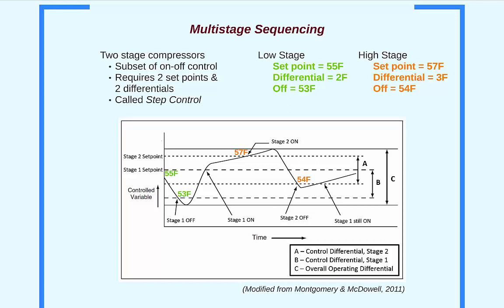This step control can be used in terminal heat pumps like you might see in a hotel, as well as in commercially sized VAV and multi-zone CAV systems. Additionally, larger HVAC units may have multiple compressors, each with 2 stages. Step control can therefore be an effective way to modulate capacity by adding additional compressors and stages as necessary.